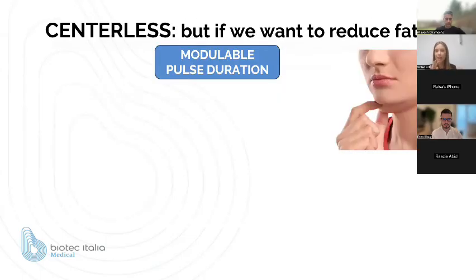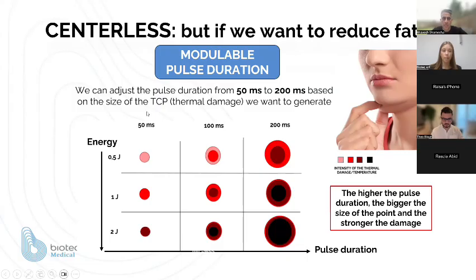So everything fine, but a lot of times people ask me, but if I really want to reduce fat in the face, for example on the double chin, where we usually have fat, what do we do in this case? In this case, we can work on the pulse duration. The pulse duration is the time we give to the ultrasound to spread and diffuse into our biological tissue. We can work from 50 milliseconds to 200 milliseconds.